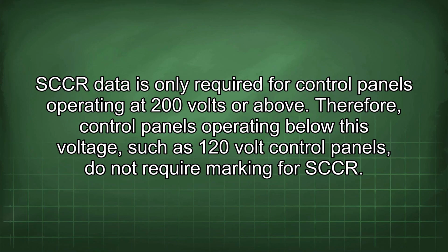SCCR data is only required for control panels operating at 200 volts or above. Therefore, control panels operating below this voltage, such as 120-volt control panels, do not require marking for SCCR.